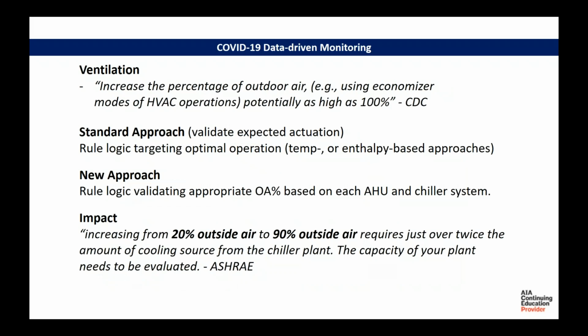The next and last piece on this is related to the guidance around ventilation. So the guide here is to keep outside air as high as possible, 100% if you can. And again, going back to FDD and how we currently monitor data, the standard way we look at economizer operation is making sure that it's not wide open in summer or that there's not a mechanical issue like a broken linkage. It's not just stuck in the same place and the OA% isn't changing. But the new logic will be to make sure that the outside air damper stays in the position that you've deemed appropriate whenever the building is occupied. So that's also good guidance, I suppose. But the real challenge is that someone has to figure out how many different air handling units can go to 80%, to 90%, to 100% before you reach capacity on your chillers, right?